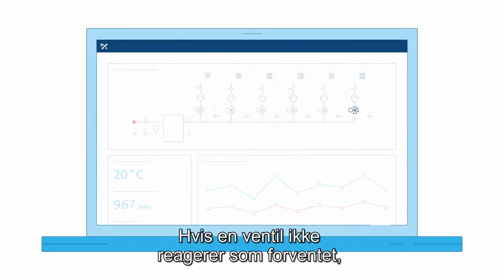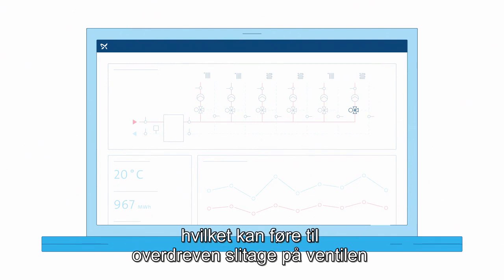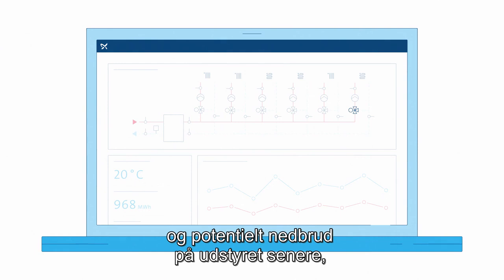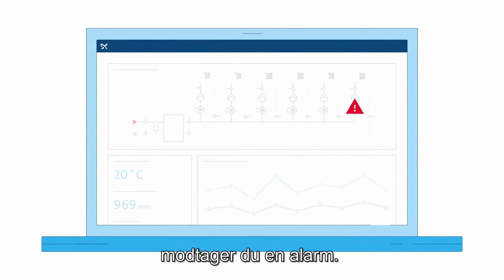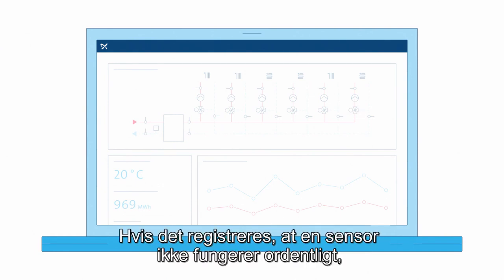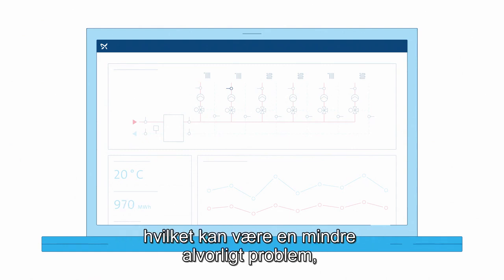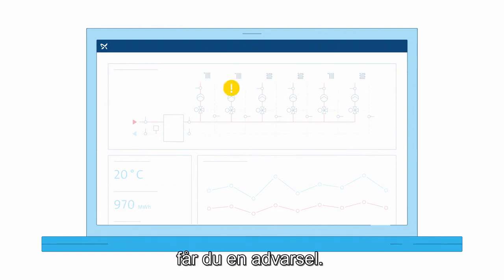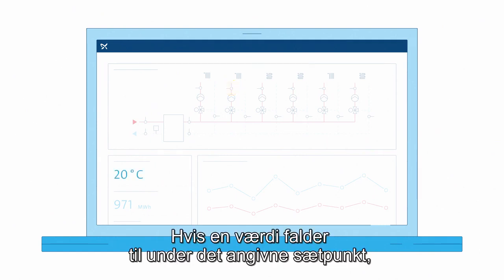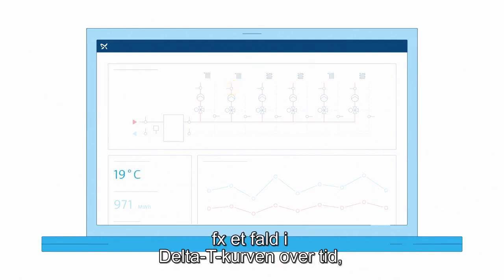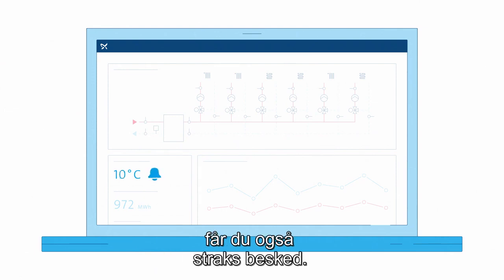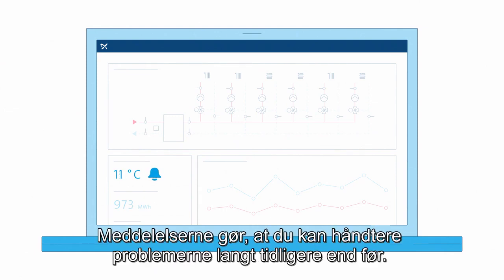If a valve isn't responding as expected, which might lead to excessive wear on the valve and potential breakdown of the equipment later on, you will get an alarm. If we detect a sensor is malfunctioning, which can be a less critical issue, you'll receive a warning. If a parameter drops below a specified set point, like a decrease in the delta T performance over time, you will get notified immediately. This lets you deal with issues much earlier.